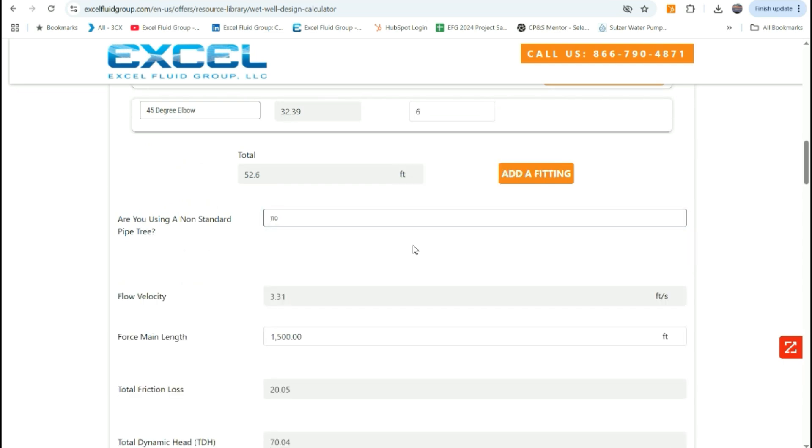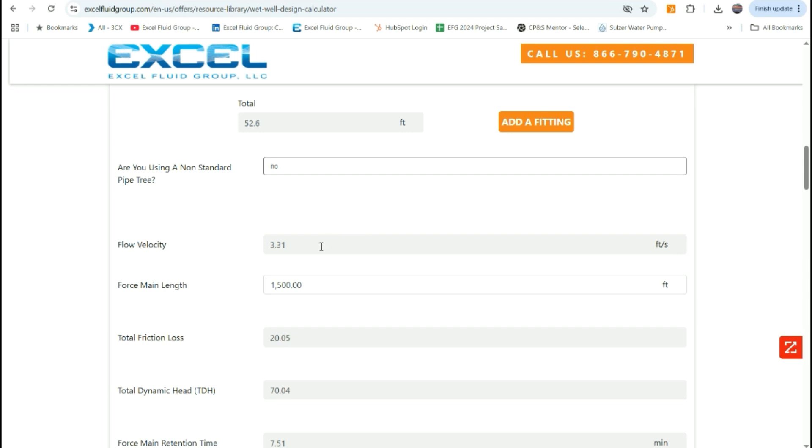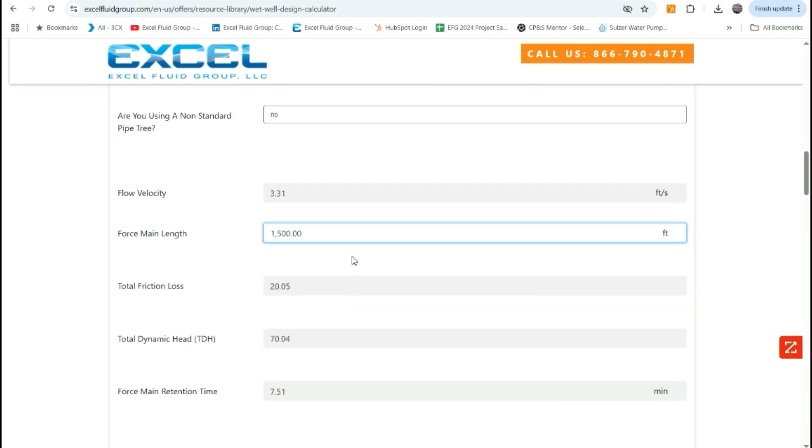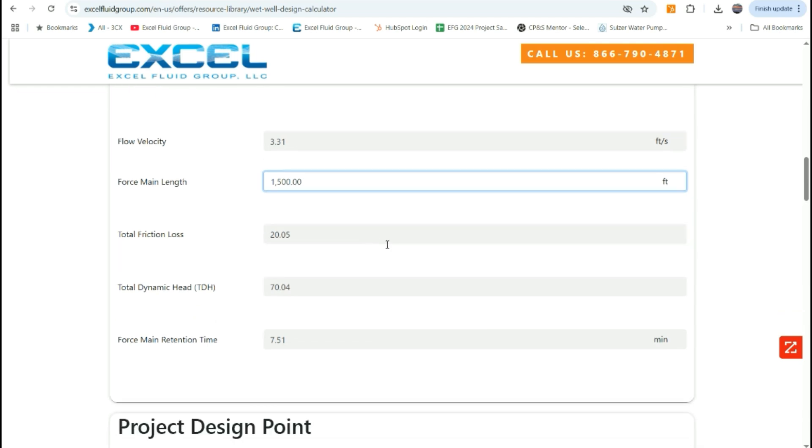From there, you can see your flow velocity in your force main. Then we'll need to take your force main length number and input that into the calculator. You'll then see your total friction loss calculation and the total dynamic head calculation from your flow velocity through the force main, plus your static head, as well as giving you a force main retention time.